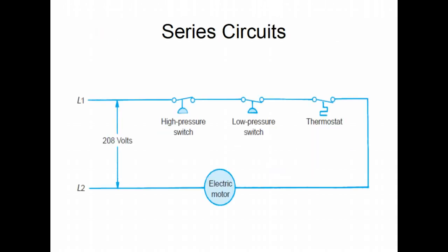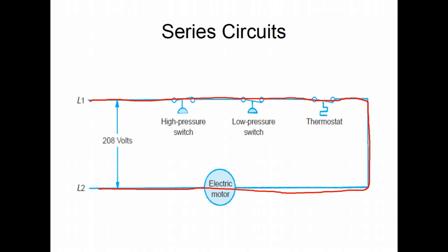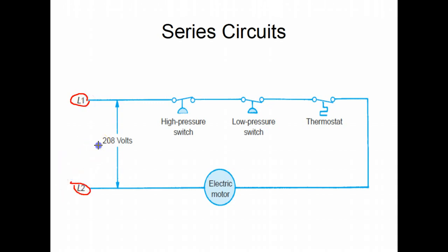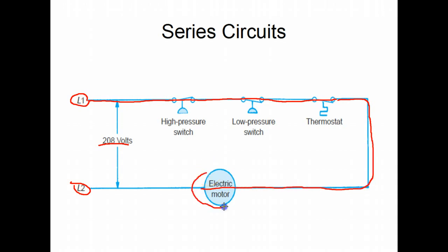The first circuit we're going to look at is a series circuit. It's called a series circuit because all of the components are connected in a straight line between the power source. L1 and L2 are the designators for the power coming in — we have 208 volts. We have the line or path for the current to flow. In this circuit we have one switch — the high pressure switch — another switch — the low pressure switch, and the third switch is the thermostat. All of these must be made or closed, and then the electric motor will operate because we have all four components needed.